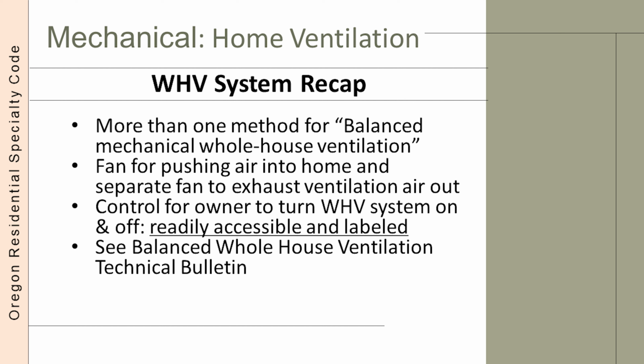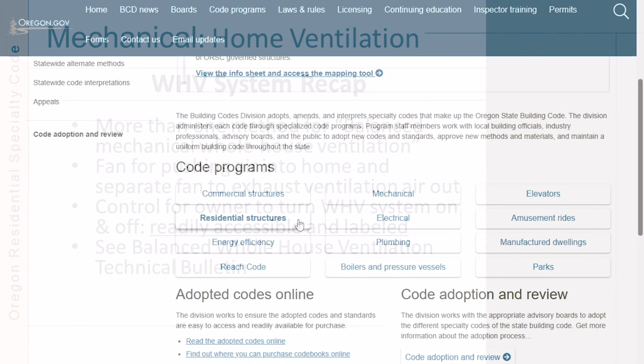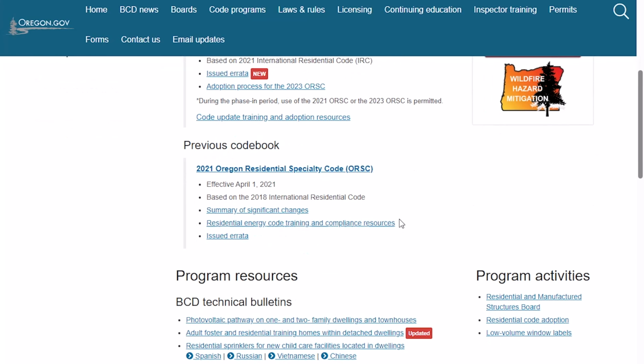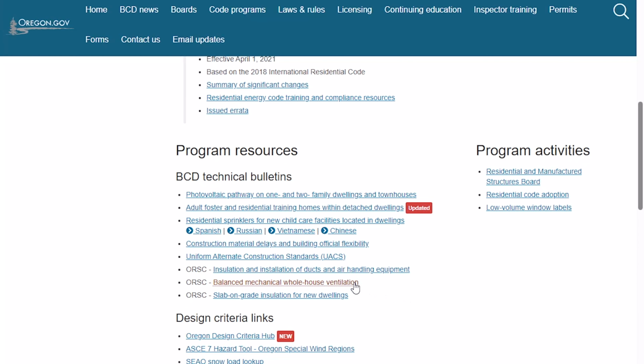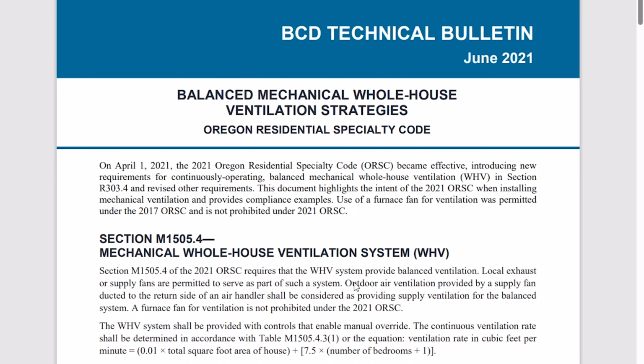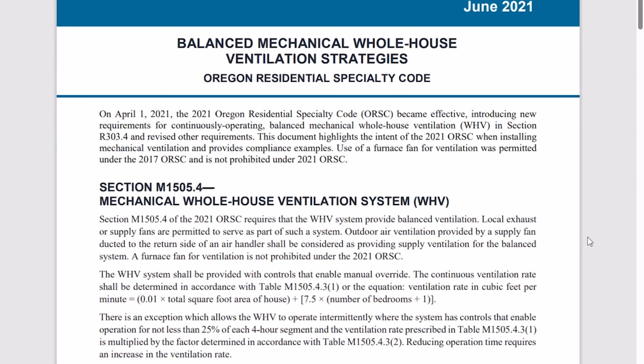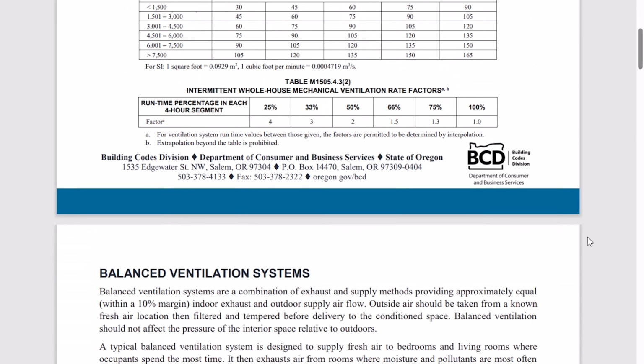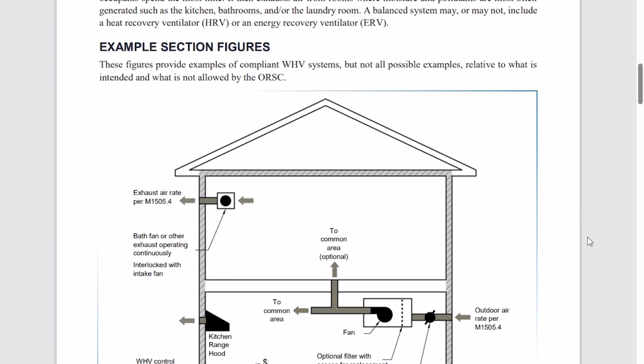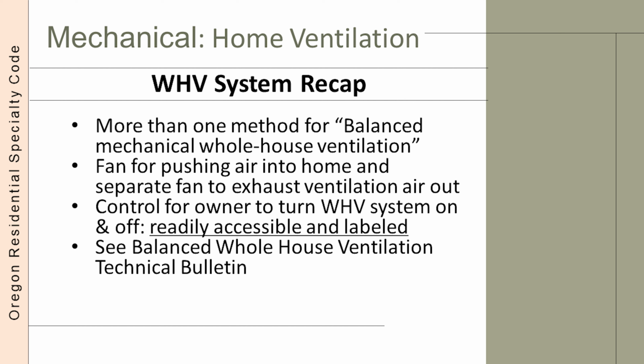Having covered special requirements for some ventilation systems, we'd like to address the whole house ventilation system requirements from Chapter 15. We have a technical bulletin that covers most of the many ways to achieve the ventilation system requirements. There's more than one way to get air into and out of a home. However, we want to emphasize that each system needs a fan or other system pushing air into the home and a separate exhaust fan that pulls the same amount of ventilation air out of the home. This is what is meant by a balanced ventilation system. The push and pull fans have to be interlocked so that the system can be controlled by the owner. That control, usually a wall switch, must be readily accessible to the owner and clearly labeled.